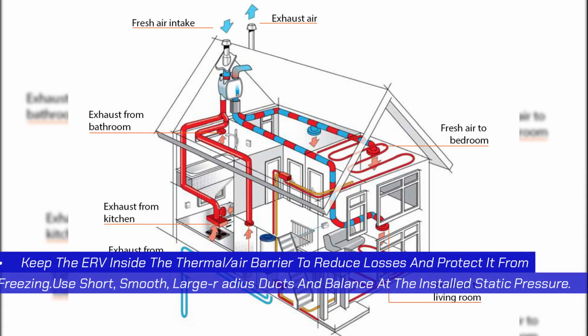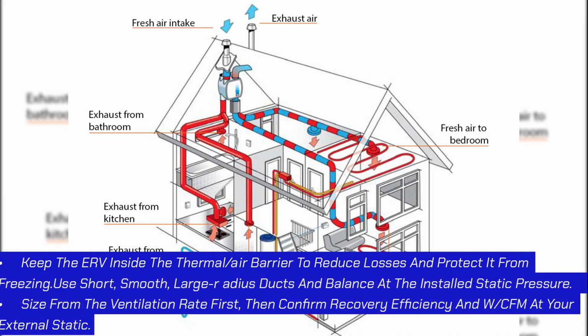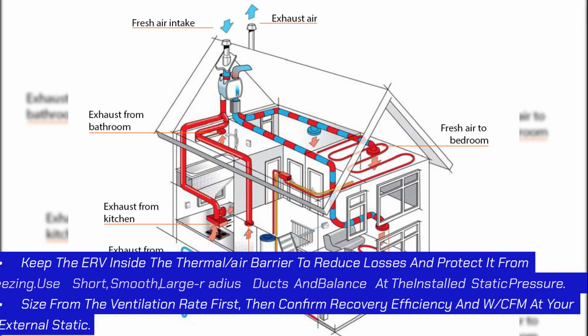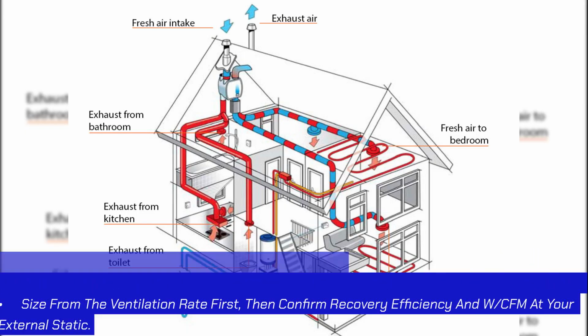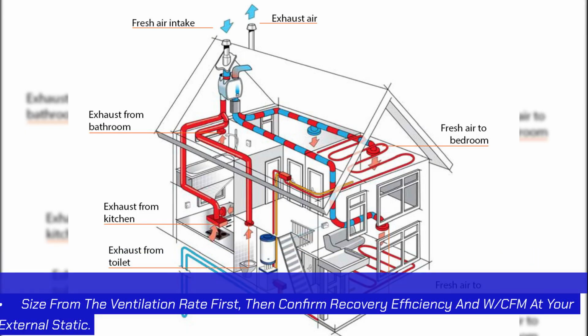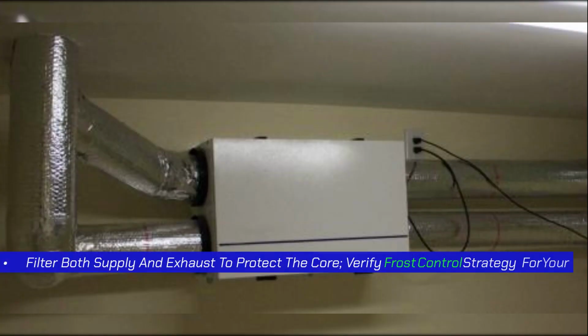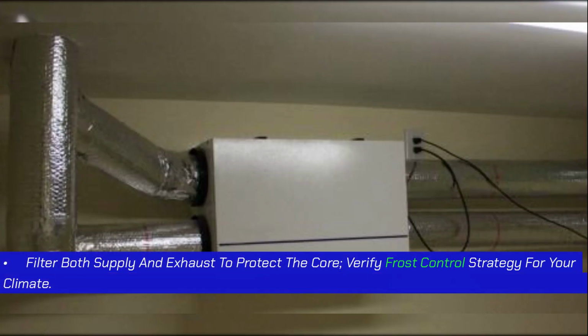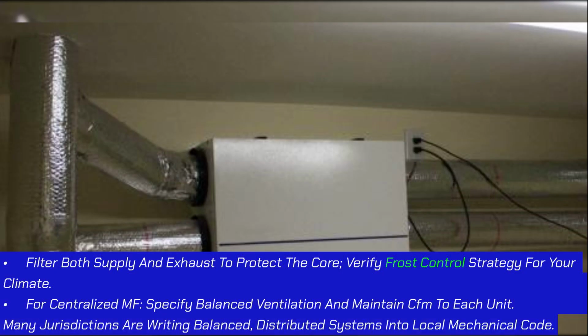Keep the ERV inside the thermal air barrier to reduce losses and protect it from freezing. Use short, smooth, large radius ducts and balance at the installed static pressure. Size from the ventilation rate first, then confirm recovery efficiency and W, CFM at your external static. Filter both supply and exhaust to protect the core. Verify frost control strategy for your climate.